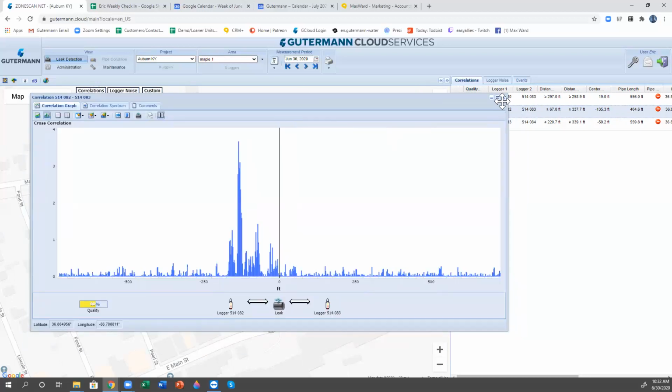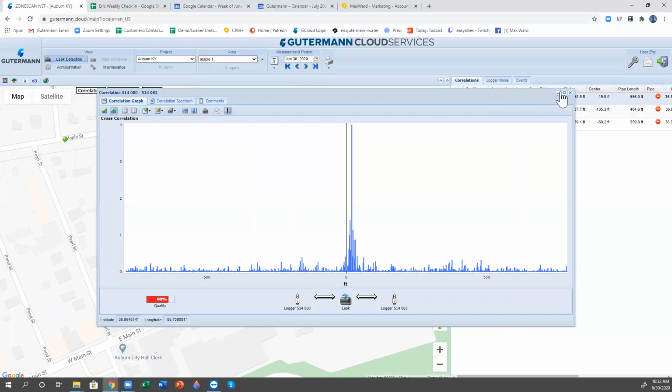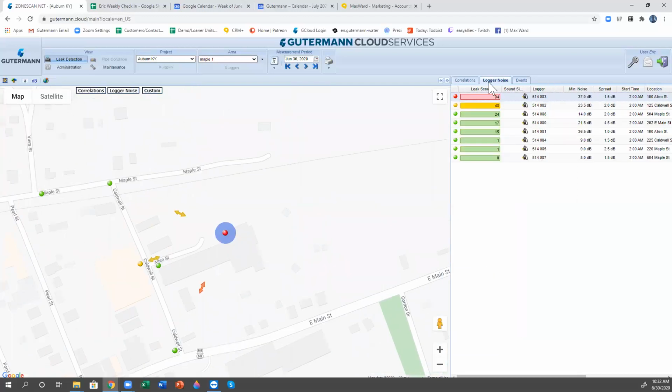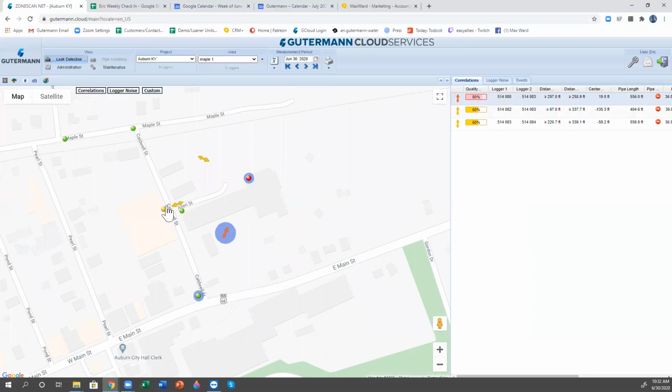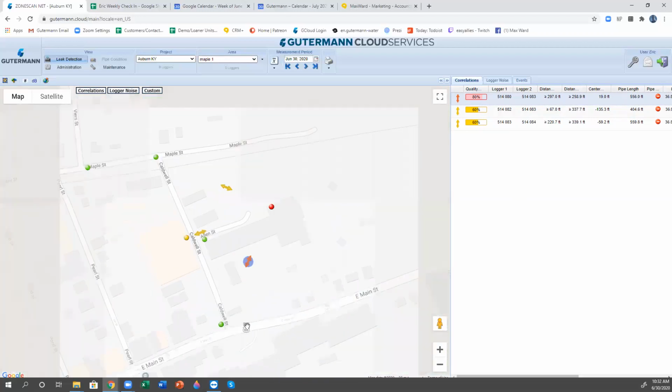The one correlator that heard the 94 was on a 2-inch galvanized. Okay. Found one, huh? Yeah, somewhere underneath Allen between there. All right. Let's draw in the pipe. 2-inch back towards the street somewhere. Which Allen is this? Off Caldwell Allen. So this pipe, how does it go? Is it just a straight line here and then a service connection here? Yeah, it goes pretty much straight out over to Caldwell from there.